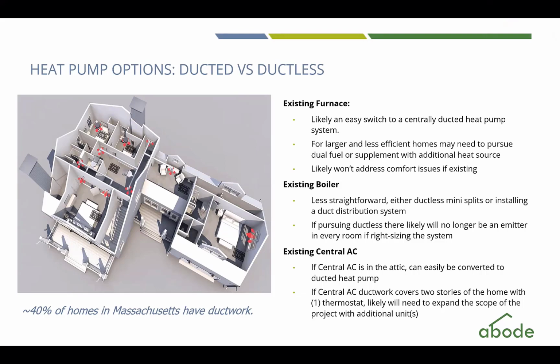For homes that have ducted systems, can they go to ductless? Yeah, so sometimes mixing and matching ducted and ductless could certainly make sense. Say if the ductwork is in really bad shape, very leaky, and it may have asbestos on it, then maybe you don't want to be using that duct distribution system and you go with designing with ductless. Where I think it makes the most sense to mix and match ducted and ductless is if there's a room that has different thermal characteristics.